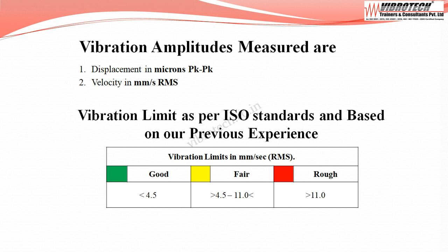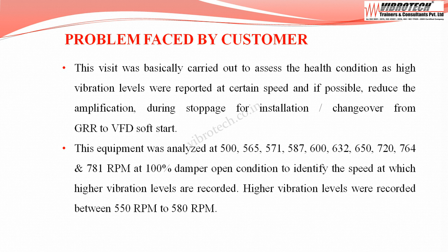This equipment was analyzed at various RPM at 100% damper open condition to identify the speed at which higher vibration levels are recorded. Higher vibration levels were recorded between 550 RPM to 580 RPM. The table shows the measured values of maximum velocity recorded in the fan drive end bearing horizontal direction at various RPMs.